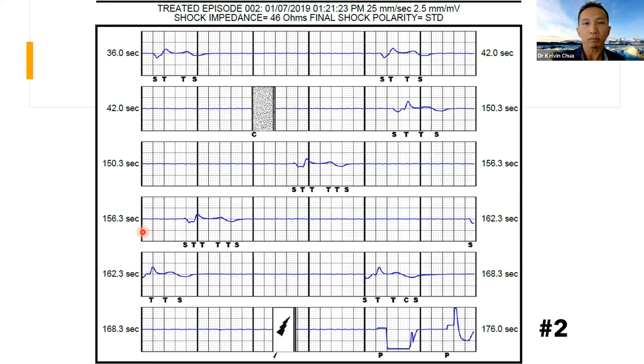The main reason of bringing this talk up is that the S-ICD, because of its subcutaneous nature and the possibility of undersensing intracardiac signals, sometimes long pauses with sense intervals are discarded and it continues to count following long pauses. That is why after a long pause, the device continues to detect tachycardia up to a point where detection criteria is satisfied and the device charges up and delivers shocks.